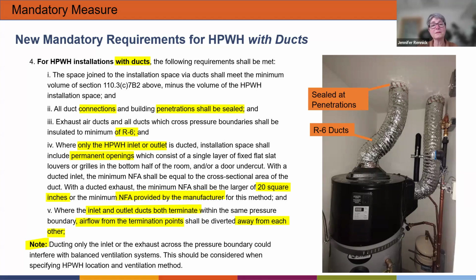And so with ducts, the big thing here is that you're going to be looking at the penetrations with the ducts being sealed. But because of this too, you need to make sure the duct diameter is of a certain size, or that the net free area of that duct itself either meets the manufacturer's specification, or, you know, you're going to have 20 square inches, for example. And that's if you're going to have an exhaust duct only.